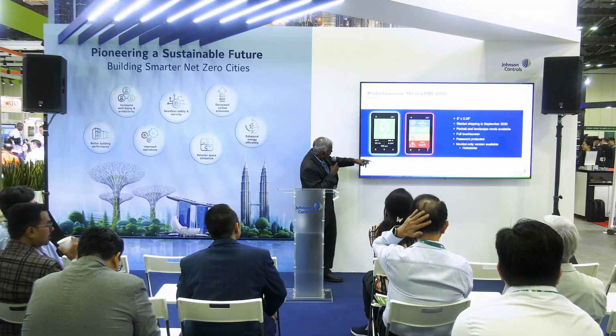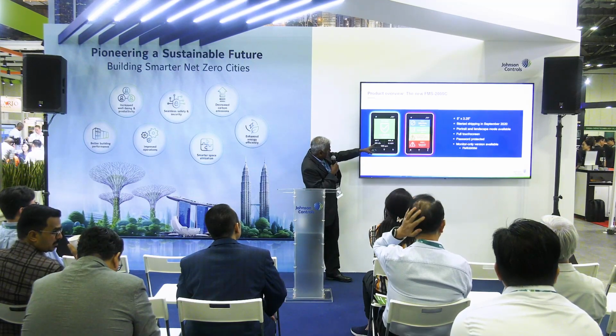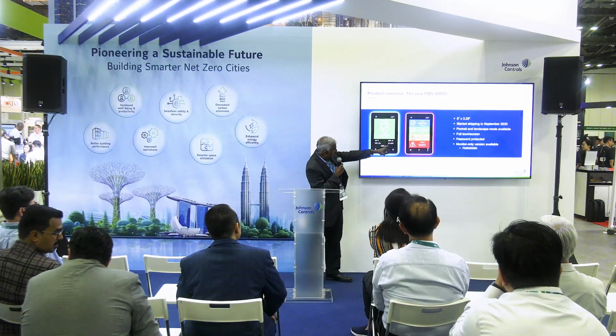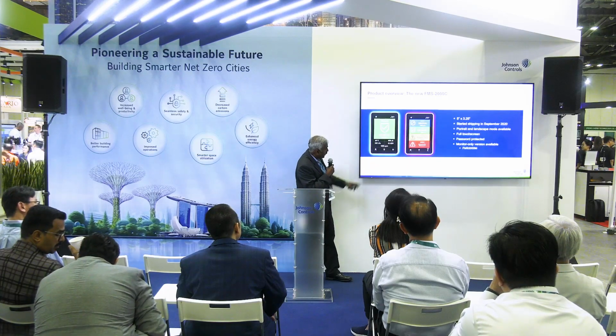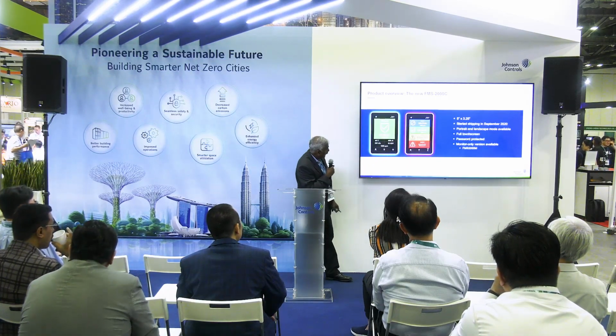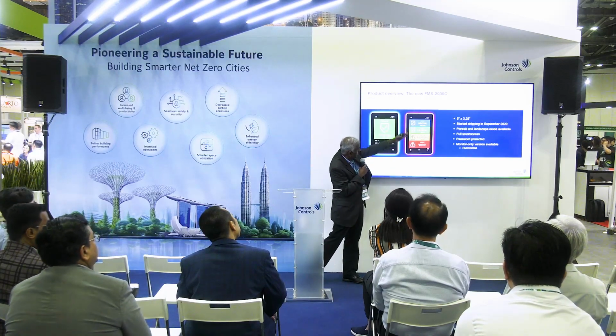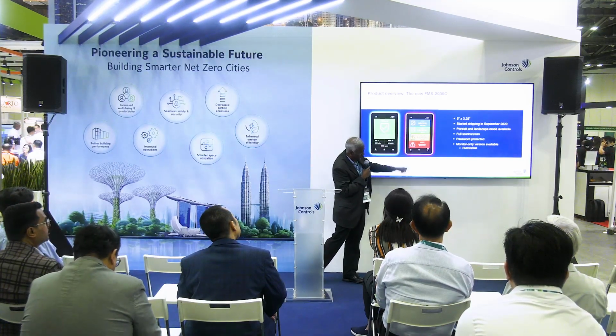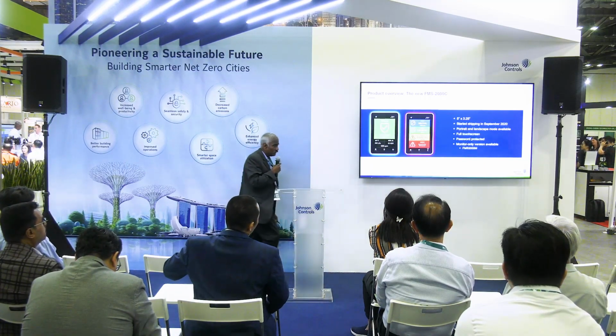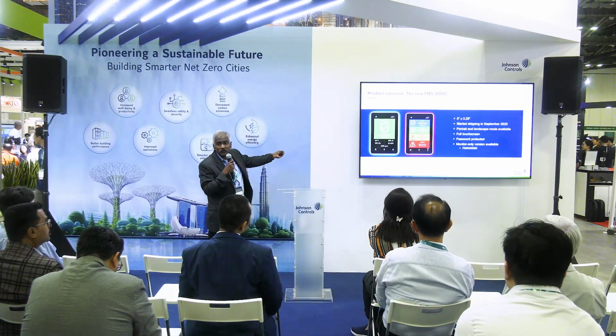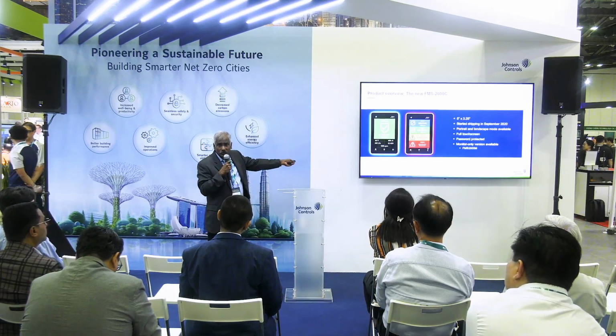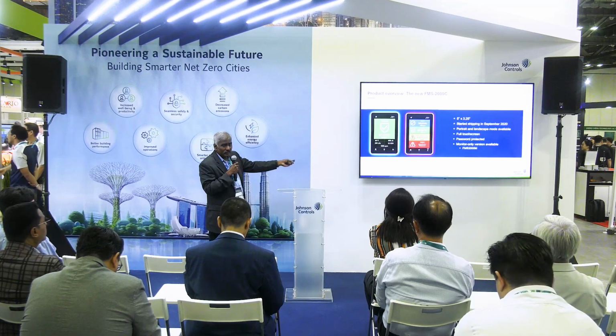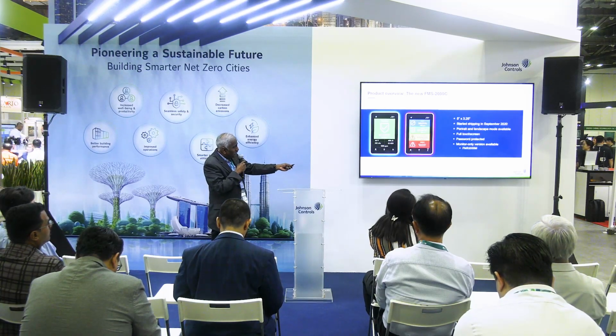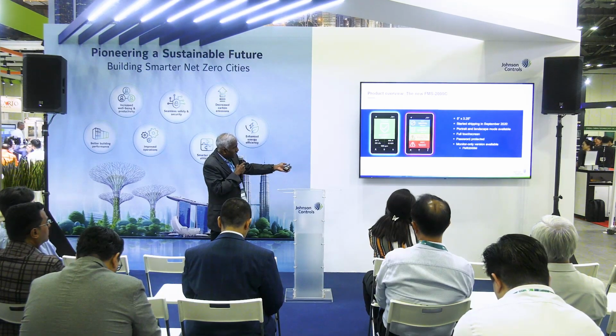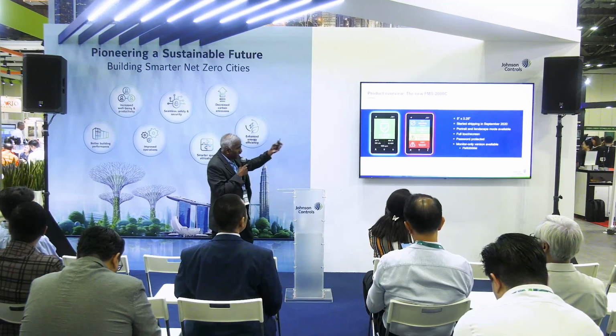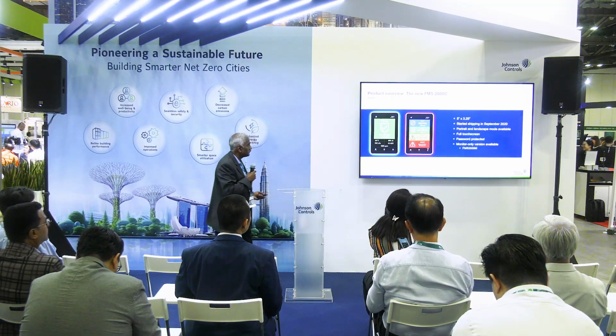So you look over here - it shows the temperature, CFM, number of air exchanges, and even ppm. You have an audible alarm, and another display that shows multiple readings - you can have up to 6 displays in a room, and this connects to the Venturi valve. This is basically the controller where you put in all the sensors - temperature, CO2 sensors, differential pressure - all goes in, and you have a nice display, a halo display.